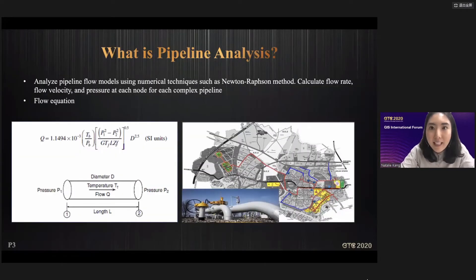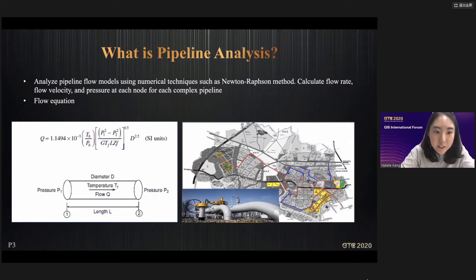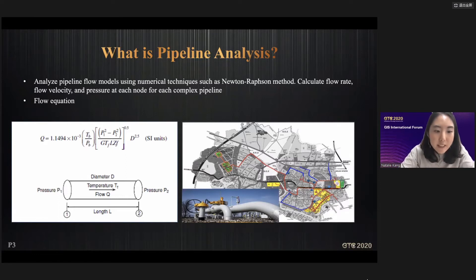What is pipeline analysis? Our pipeline analysis solution, which we named PLUS, is the introduction of numerical analysis techniques into the gas industry. The input elements used as the basis for the models are gas pipes, valves, and gas governors. The gas pipe model is represented by the flow equation Q — we can calculate the flow rate, flow velocity, and pressure in the pipeline using numerical analysis. If you apply a mathematical model like the left-side picture to the entire city, it will look like the right-side picture.